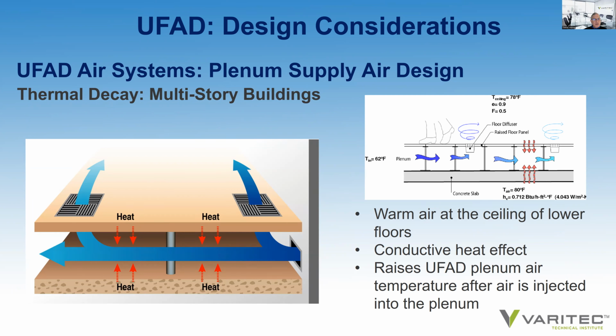If air is injected at the interior zones of a UFAD plenum, that air has to migrate across the surface of the concrete slab. If the air under the slab is at 80 to 85 degrees, the conductive heat effect through the slab will heat the supply air in the plenum. And the longer the air has to travel under the plenum, the more heat is absorbed into that supply air. So consequently, the air supplied at diffusers at the perimeter zone will be warmer than the air coming from diffusers mounted on the interior zone.